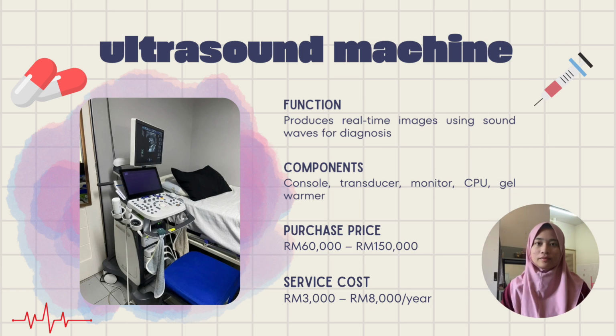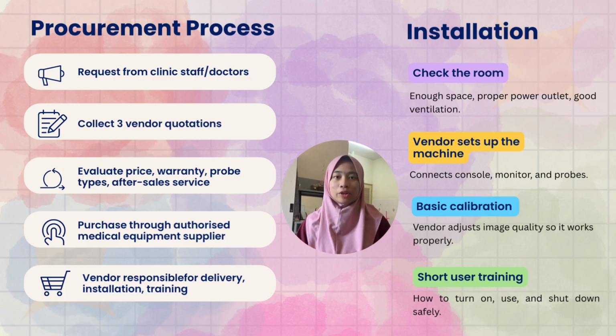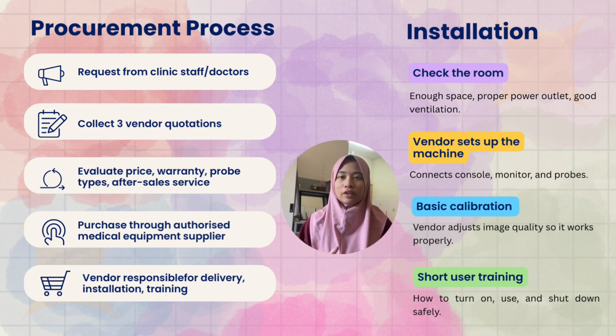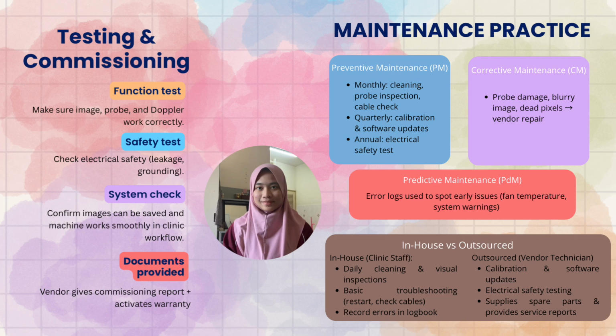diagnostic images. The ultrasound machine is procured through an authorized medical equipment vendor after obtaining quotation and management approval. The vendor is responsible for delivery, installation, and initial setup. During installation, checks are performed on room suitability, power supply, and system configuration to ensure the machine meets manufacturer requirements before use. Before clinical operation, the ultrasound machine undergoes testing and commissioning, which include functional testing, electrical safety testing, and system verification. Calibration is also performed to ensure accurate image quality.